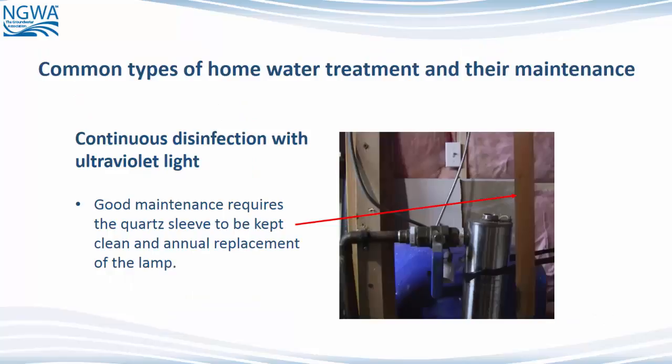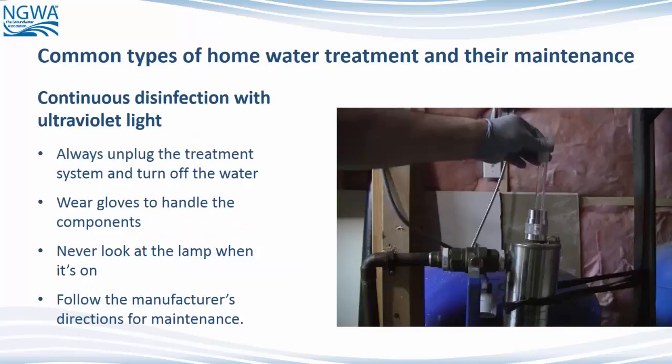Good maintenance requires the quartz sleeve in which the lamp is enclosed to be kept clean, and good maintenance requires annual replacement of the lamp. When performing maintenance on a UV light system, always unplug the treatment system and turn off the water. Wear gloves to handle the components. Never look at the lamp when it's on, and follow the manufacturer's directions for maintenance.